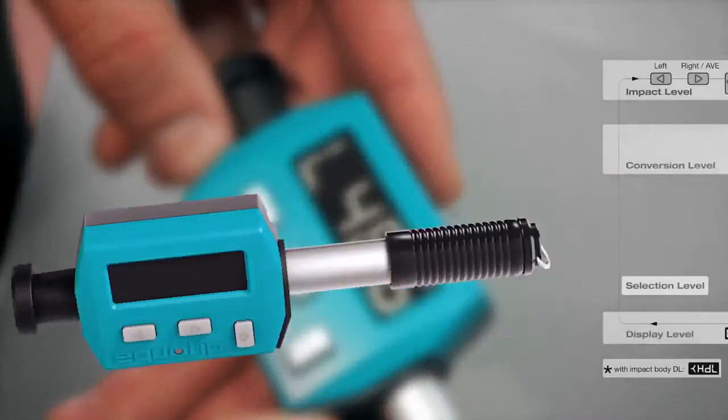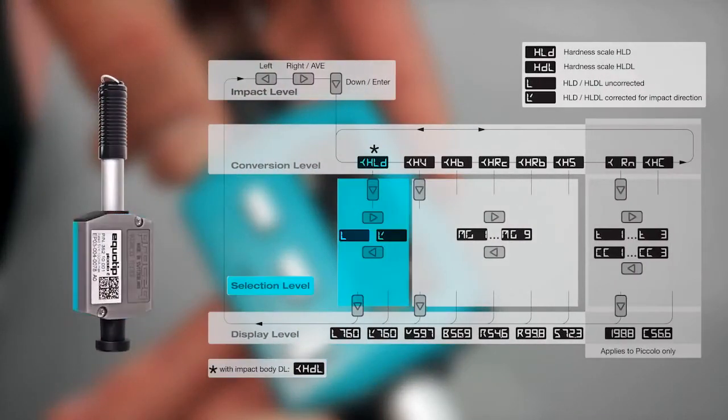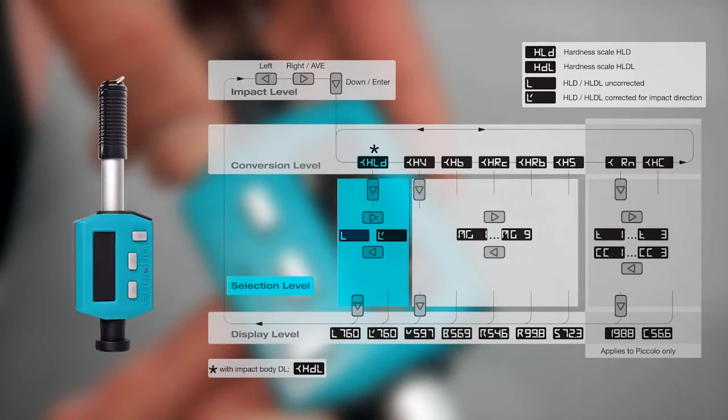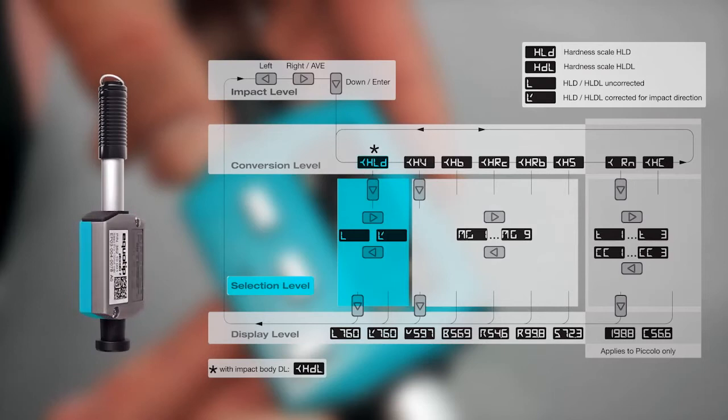If you choose Leeb, you can select L, which allows you to use the original uncorrected Leeb value. Otherwise, the value is always corrected for impact direction. Most measurements with the Ecotip Piccolo are performed in the average mode. This means that a series of impacts is performed and the instrument displays the average value of these impacts when completed.